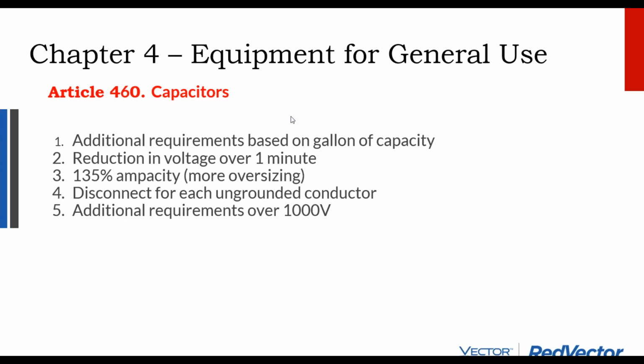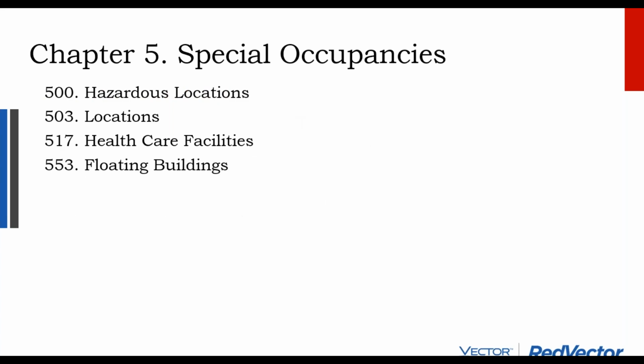And so as a building engineer, with solar and batteries becoming more prominent, you may find yourself needing to take a master electrician exam, for instance, and you say, well, what are all the sizing considerations? Typically, you're oversizing your conductors by 25% when it comes to electrical design. There are special exceptions. Solar is one of them. We'll talk about why a little bit later. Capacitors are another one of them. Capacitors get a 35% oversizing. And I believe that's just because capacitors can be so rapidly discharged.